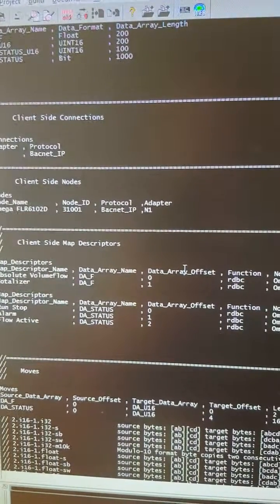And because it's BACnet and we're reading analog data, it's reasonable to assume we're going to get a floating point. Okay, we could apply some scaling at the end there. In this case, the scaling is non-effective. We are doing 0 to 100 maps onto 0 to 100, so we're not changing the value at all. The engineering units are not relevant because we're just reading a number and serving on Modbus, and in Modbus we can't tell it the engineering units.